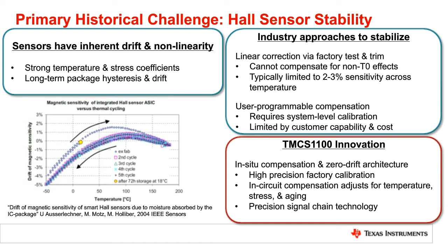What TI has done with the TMCS1100 is try to innovate in the way that these sensors are compensated by adding in situ compensation on the IC itself, as well as pairing that with the zero drift analog front end architecture. And this allows us to do a high precision factory calibration at time zero, and then the circuit itself compensates and continually adjusts for temperature, stress, and aging. That eliminates most of these package hysteresis and lifetime effects, as well as greatly improves the temperature performance of the chip. And this is really enabled by TI's precision signal chain technology, both in circuit design as well as in our process technology to build more stable analog front ends and Hall sensors.